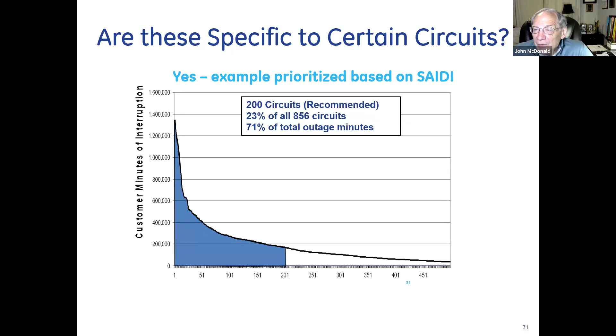We find that only 200 of the circuits account for 71% of all the outage minutes of the utility. So if we automate just 200 circuits, we address about three-fourths of the total outage minutes. That's a much better use of budget money.